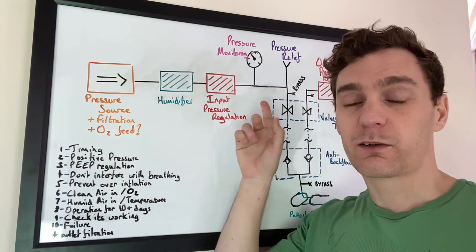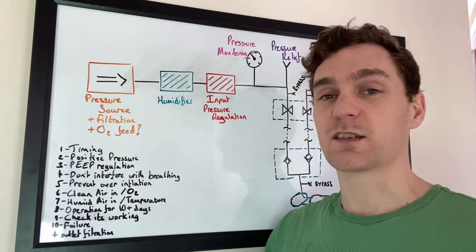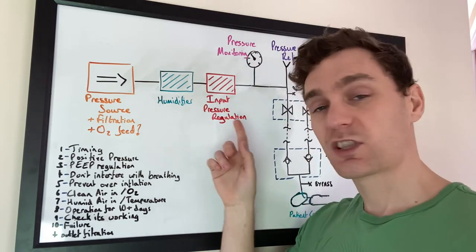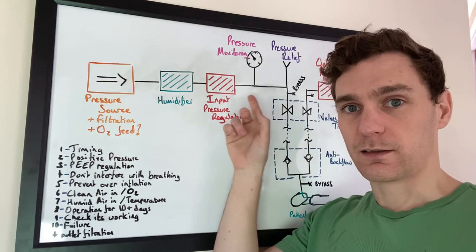Pressure monitoring. This is very important for the clinician to make sure that the right amount of air, the right pressure of air is being delivered to the patient. Not just being able to set it but being able to check that what you set is actually what's being delivered.